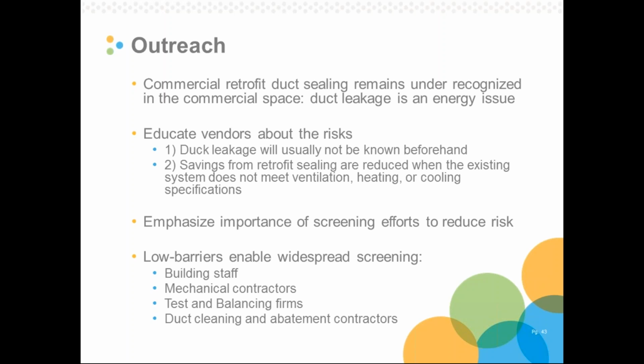There still remains some skepticism on the efficacy of duct sealing, and I hope I've shown you today that, if nothing else, retrofit duct sealing does work. We need to educate the vendors about duct sealing, about the energy issues, but we also need to educate them about the risks. We need to get people comfortable with the idea that duct leakage will usually not be known beforehand. There's also another part of this, which is that savings from retrofit duct sealing are reduced if the existing system is not meeting its goals. If it's not ventilating, heating, or cooling properly due to duct leakage, and we fix that duct leakage, that will reduce our energy claims. That said, if a building is failing to meet its basic services, there are obviously non-energy reasons for sealing our ducts.